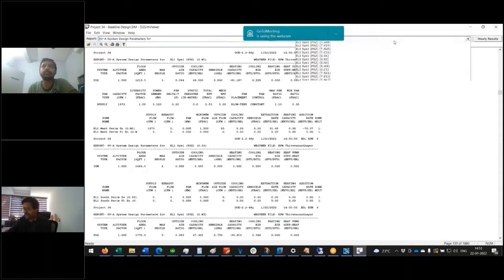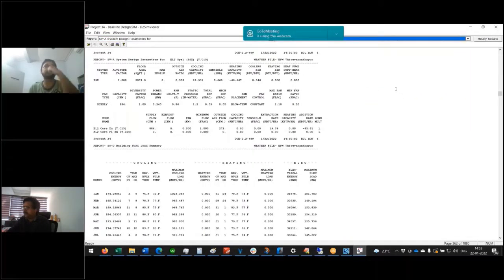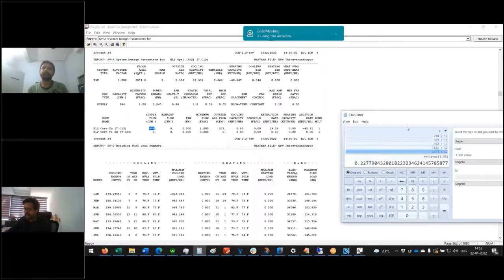How would I address it? I'll then go to SVA. I'll look at this TC15. Now what I can see is the floor area is 3074 square feet, right? 3074. And the CFM that I see is 884. So if I divide 884 by 3074, I'm getting 0.28 CFM per square feet, which is practically speaking very low.